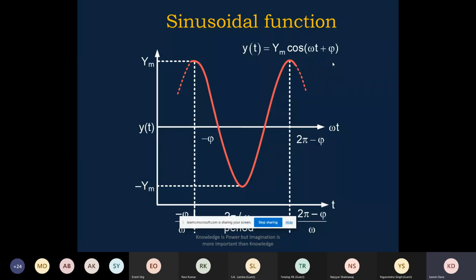We can also consider sin(omega t plus theta), but the advantage is that the PMU works on a real time clock and timestamp, so it can calculate on Ym cos(omega t plus theta). But that is called the phasor calculation. PMU means phasor measurement unit. I think you must be acquainted with the phasor measurement unit.